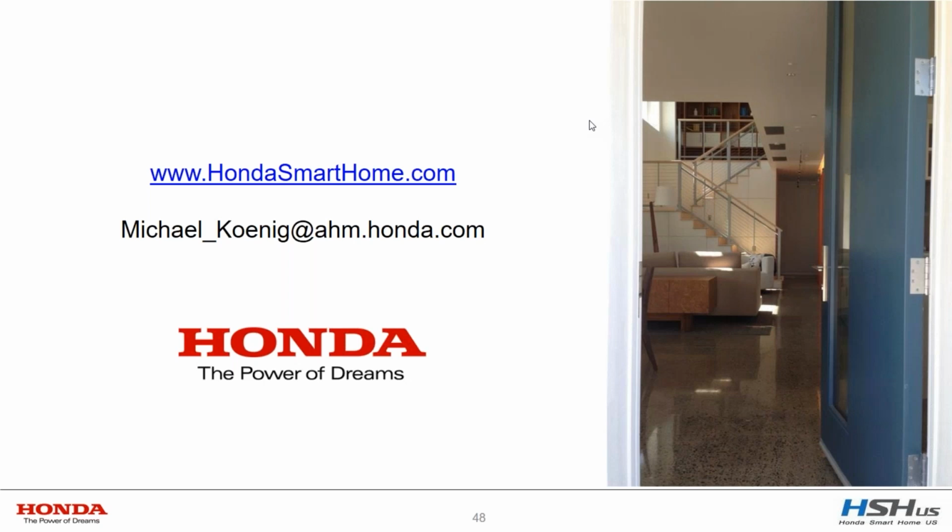The ERV question came out in the very initial design phase, because everybody knows a couple of things always pencil: solar hot water and an ERV. But in our case, when we looked at the numbers, because we were ventilating at preferential times of day, we were taking cool air in instead of hot air most of the time. The additional fan loads of the ERVs didn't pencil for our house. But I've seen some of the small ERV and HRV systems that fit in joist space, and I think those are fantastic designs. They just didn't pencil here because we were so carefully controlling when we were ventilating anyway.